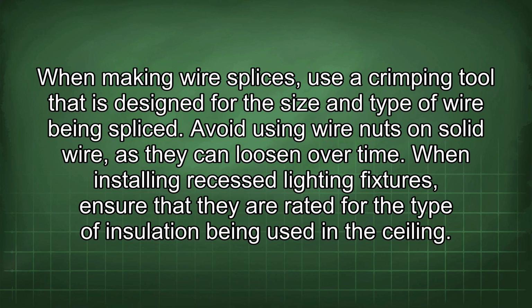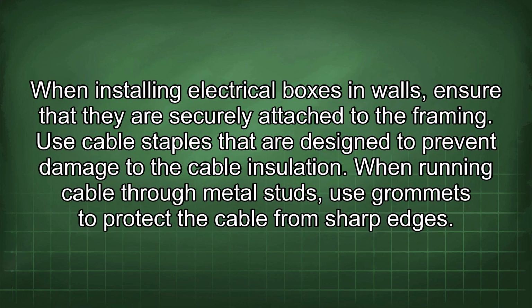When installing recessed lighting fixtures, ensure that they are rated for the type of insulation being used in the ceiling. When installing electrical boxes in walls, ensure that they are securely attached to the framing. Use cable staples that are designed to prevent damage to the cable insulation. When running cable through metal studs, use grommets to protect the cable from sharp edges.